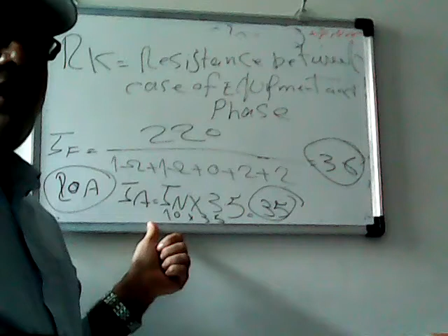Over here, we have to substitute, or also put a fuse, or substitute a protective circuit breaker in industrial, commercial, and building settings. We should add, in addition to the fuse, an earth leakage circuit breaker. We talk about what the earth leakage circuit breaker will do to cut out the short circuit, even if our fuses are 50 ampere, 60 ampere, even 80 ampere.